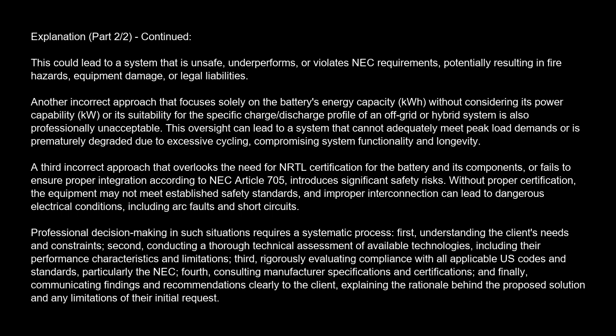This oversight can lead to a system that cannot adequately meet peak load demands or is prematurely degraded due to excessive cycling, compromising system functionality and longevity. A third incorrect approach that overlooks the need for NRTL certification for the battery and its components, or fails to ensure proper integration according to NEC Article 705, introduces significant safety risks. Without proper certification, the equipment may not meet established safety standards, and improper interconnection can lead to dangerous electrical conditions, including arc faults and short circuits.